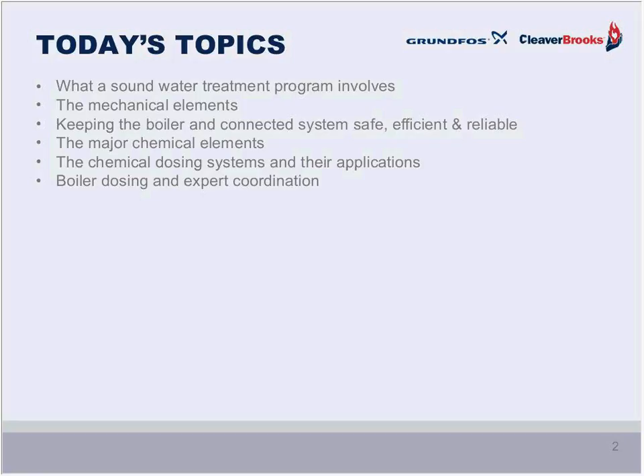Boiler dosing and expert coordination. What he will be stressing here is the importance of the pump manufacturer, the dosing pump manufacturer, and the chemical treatment consultant. There's an understanding between those two in terms of what is going to be used, how it will be dosed, and so on, because that's going to affect the pump, and we'll discuss that. With that, of course, will be the dosing pump details, key points to be aware of, and the system options.